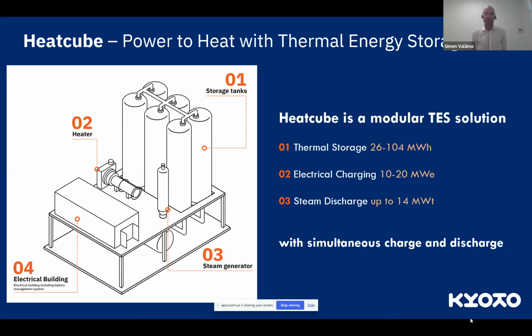An important aspect of thermal energy storage when you do power to heat, that separates it from power to power, is that the charging side, where you use electricity, and the discharging side, where you produce heat, are disconnected, which allows a thermal energy storage asset like the Heatcube to do simultaneous charge and discharge.